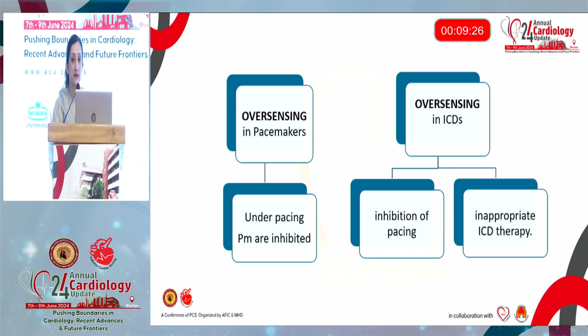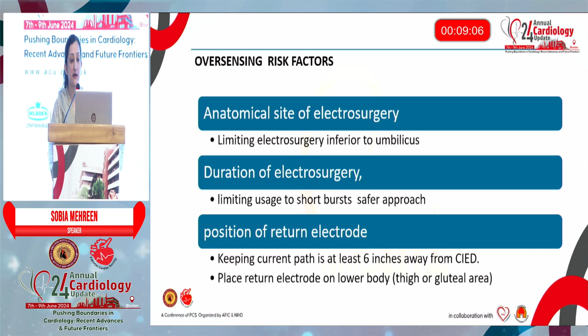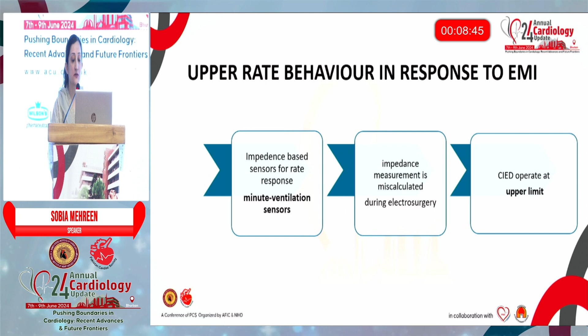The risk factors of oversensing depend on anatomical site of electrosurgery, duration of electrosurgery, and the position of return electrode. Limiting electrosurgery to procedures below the umbilicus, limiting usage to short bursts, keeping the current path at least 6 inches away from the device with return electrode placed on lower body can mitigate these problems. The upper rate behavior in response to electromagnetic interference occurs in patients having rate response sensors, specifically using impedance-based sensors, for example, minute ventilation sensors. It causes the device to work at the upper rate limit.